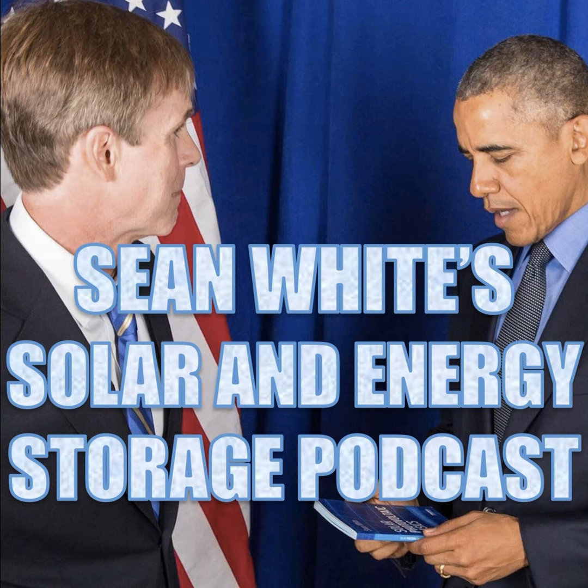So what would happen if you had one of these 200 kilowatt hour modules and just one single cell goes bad? Does it have some way to automatically bypass it, or do you need to pull out that module? The module itself at that point would have to be replaced, and that's typically what's happening - it's not an entire module going bad, it's one bad actor cell out of all of them that is the issue.